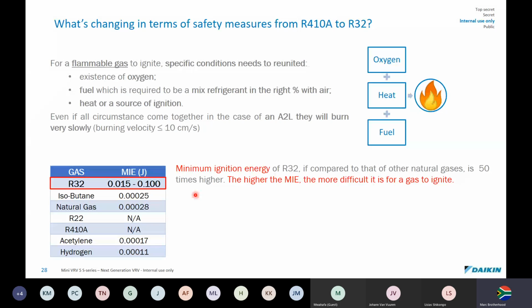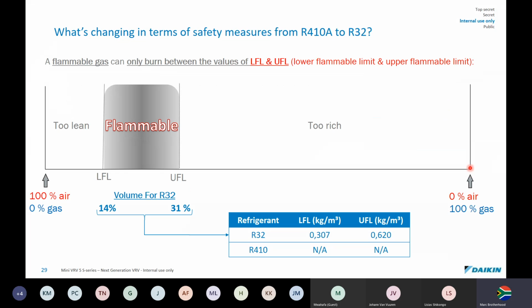If we quickly have a look at this, if you have in a room 0% air, that means you're in a total vacuum. This is a volume of air in the room. We can see that in order for R32 to burn, you have your lower flammability limit and your upper flammability limit. So when the air volume is between 14 and 31% is only when it will burn. So it's a very low flammability, these units.